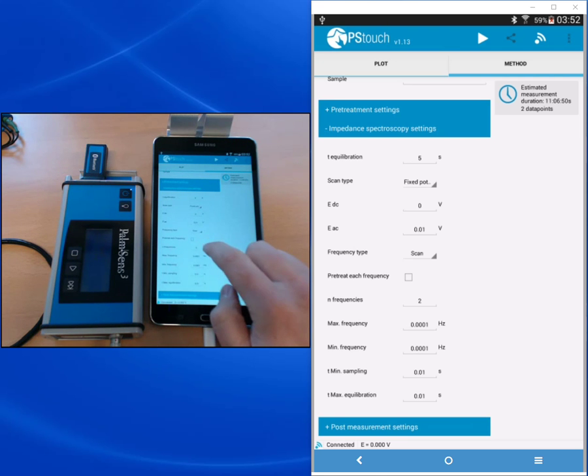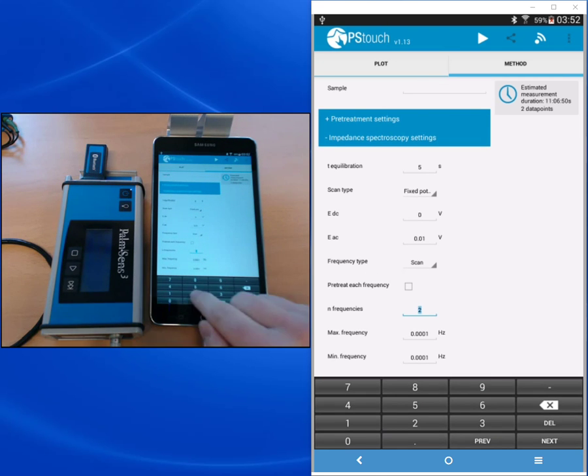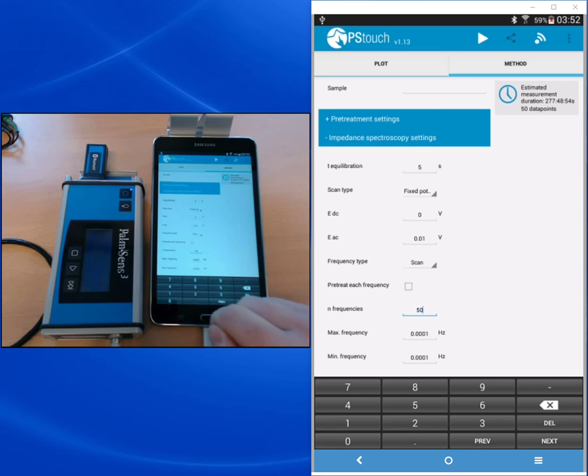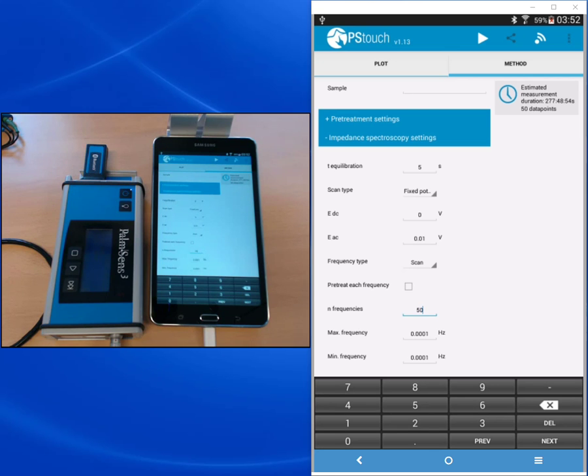So the next point is the n frequencies. This is how many frequencies. 50 frequencies measuring is fine. It also means how many points will be in the spectrum. Keep in mind that more points mean a better resolution but also a longer waiting time, especially for the lower frequencies.